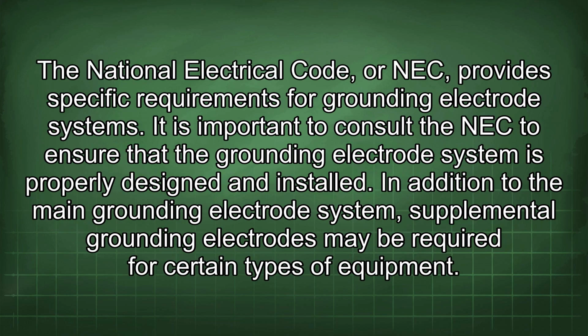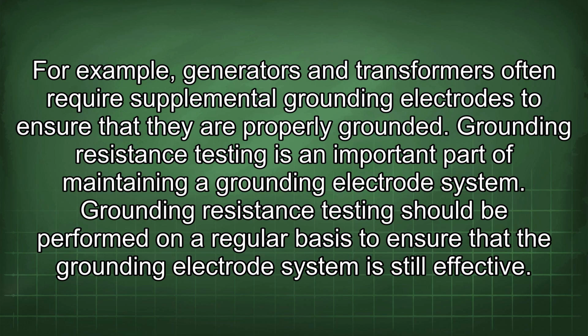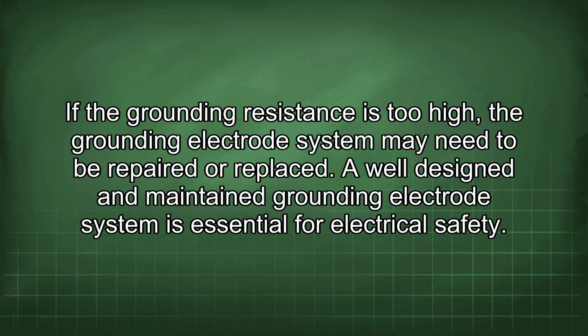The National Electrical Code, or NEC, provides specific requirements for grounding electrode systems. It is important to consult the NEC to ensure that the grounding electrode system is properly designed and installed. In addition to the main grounding electrode system, supplemental grounding electrodes may be required for certain types of equipment. For example, generators and transformers often require supplemental grounding electrodes to ensure that they are properly grounded. Grounding resistance testing is an important part of maintaining a grounding electrode system. It should be performed on a regular basis to ensure that the system is still effective. If the grounding resistance is too high, the grounding electrode system may need to be repaired or replaced.